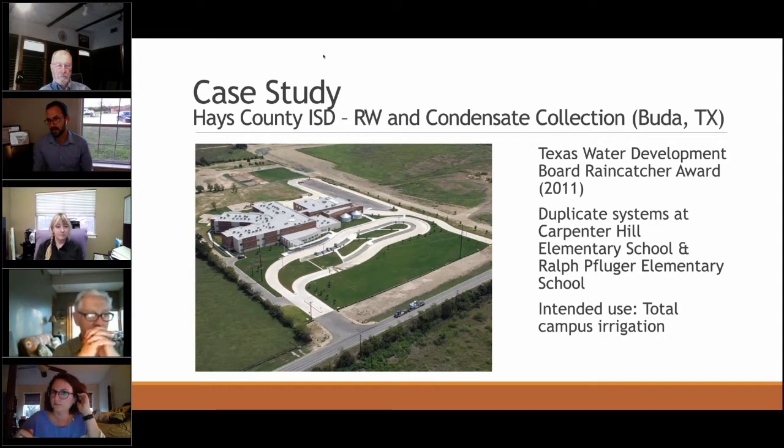The next case study is Carpenter Hill Elementary School, near 1826 and 150, completed around 2007 or 2008. This won a ton of awards for innovative rainwater design, including the Texas Water Development Board Rain Catcher Award in 2011. It's a dual-purpose system: it collects rainwater from the building's flat TPO roofs and also captures all the condensate from the school's AC system, so they're getting tremendous amounts of water in hot summer months. Ralph Pfluger Elementary followed the same design shortly after.